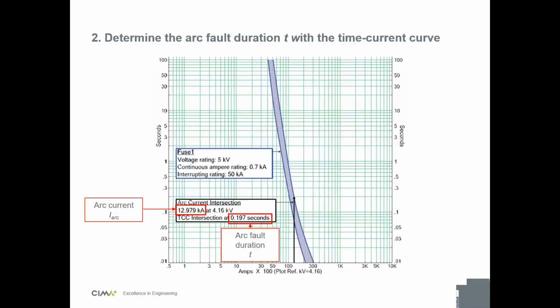So you take your arcing current. The way you read this is basically the x-axis is the current, and the y-axis is the time. So what you do is you go on the x-axis, you take your arcing current, you draw a little arrow here, and then you go up, up, up, and then you hit the right side of the fuse curve. This is the total clearing time of the fuse, and then you go to the left or to the right, and you find your arc fault duration with this time current curve.